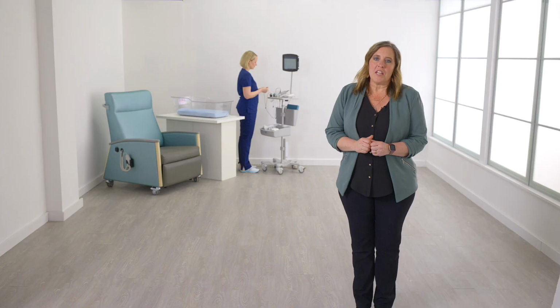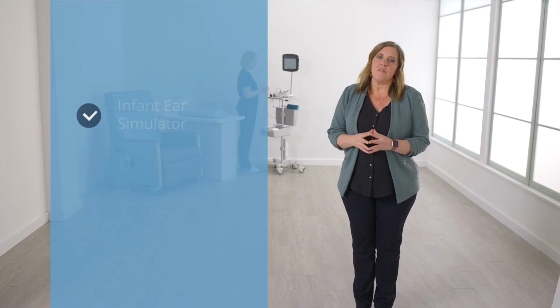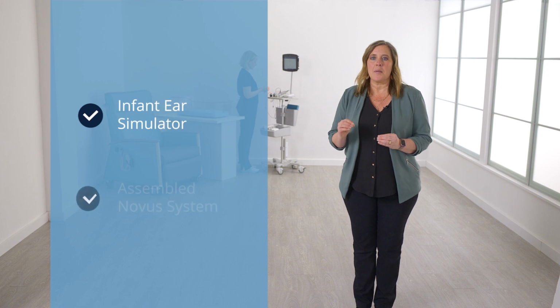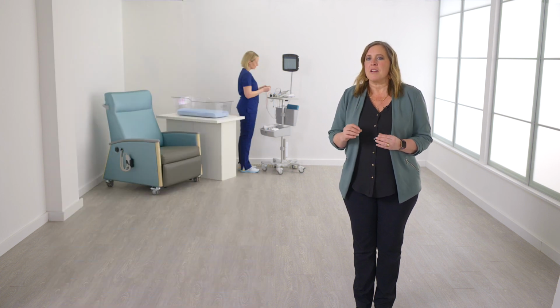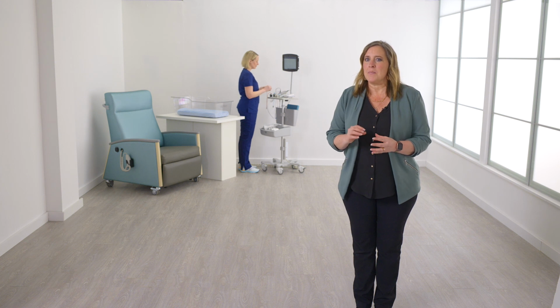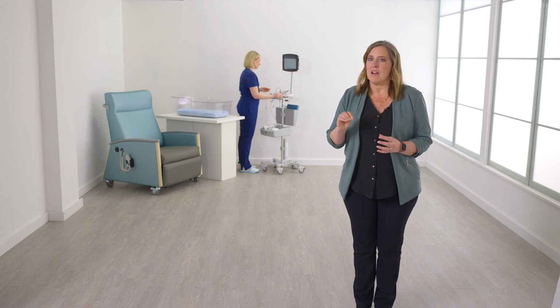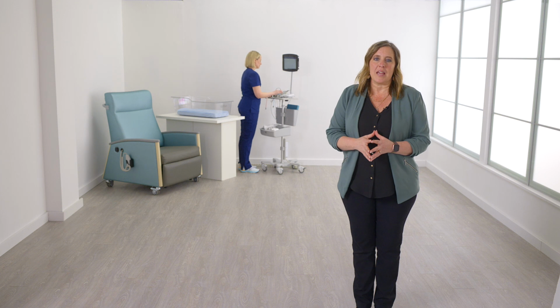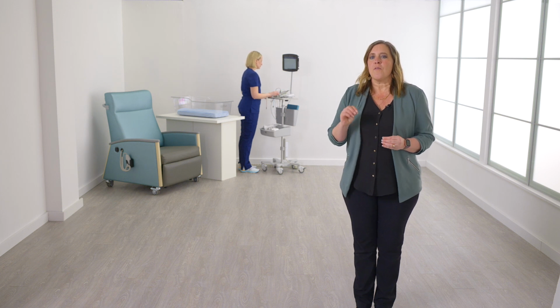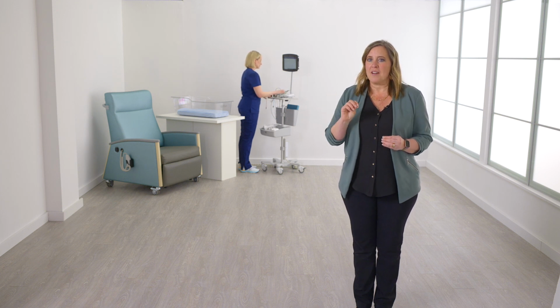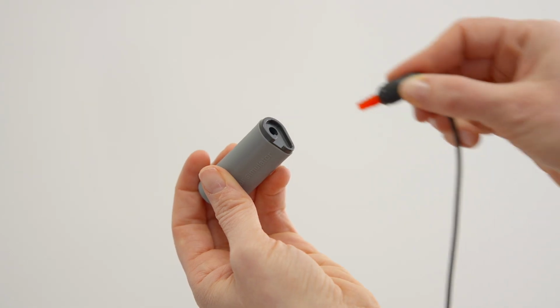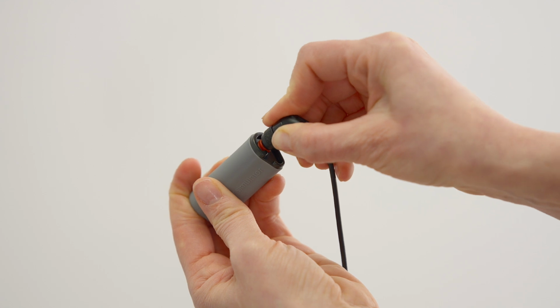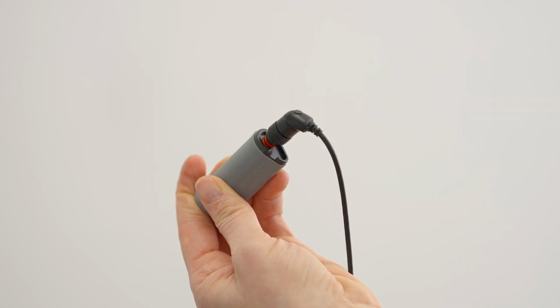To perform the quality check for OAE, you will need the infant ear simulator and the assembled Novus system used for hearing screening. The infant ear simulator is a cavity specifically designed to mimic the properties of a real infant ear so a realistic quality check can be performed. To perform the check, attach a clean red flange disposable ear tip to your OAE probe.